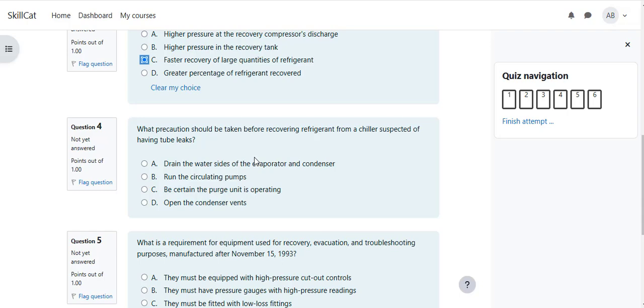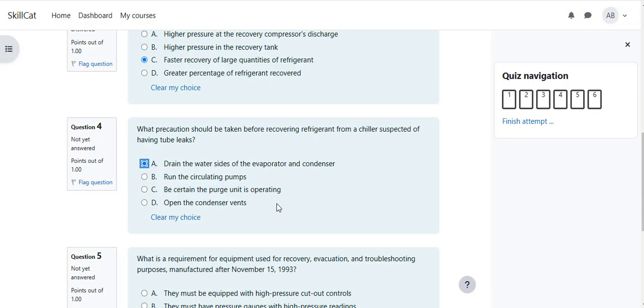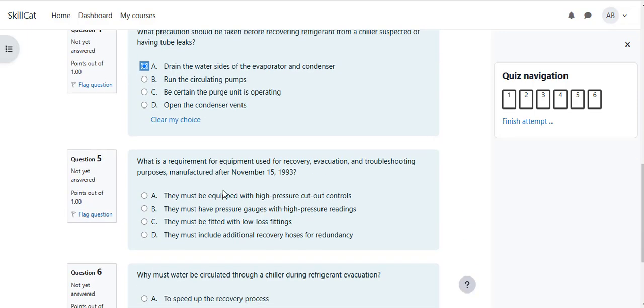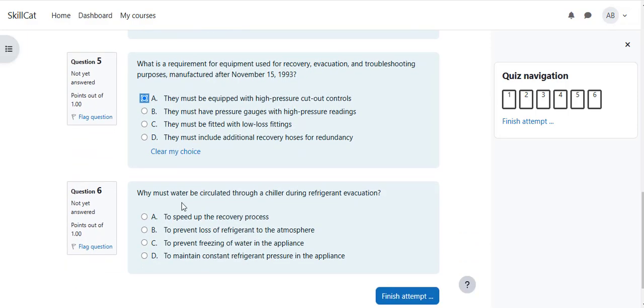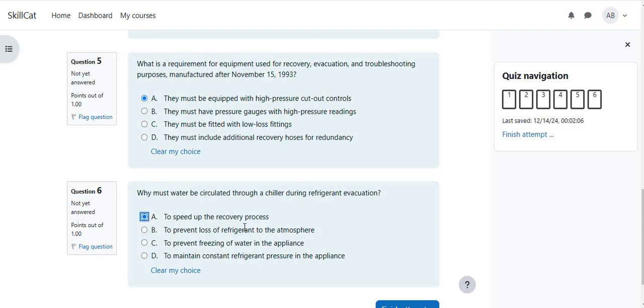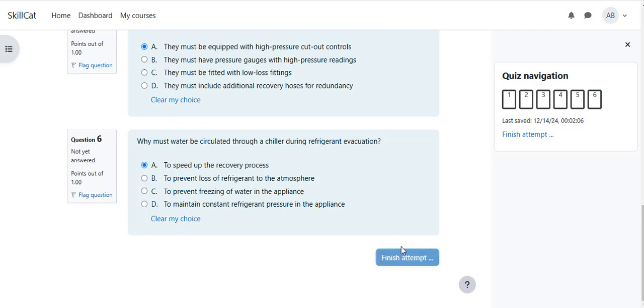What precaution should be taken before recovering refrigerant from a chiller suspected of having tube leak? Drain the water side of evaporator and condenser. What is the requirements for equipment used for recovery, evacuation, or the troubleshooting purpose manufactured after November 15, 1993? They must be equipped with high pressure cutoff control. Why must water be circulated through the chiller during refrigerant evacuation? To speed up recovery process. Okay, let's submit it and check.